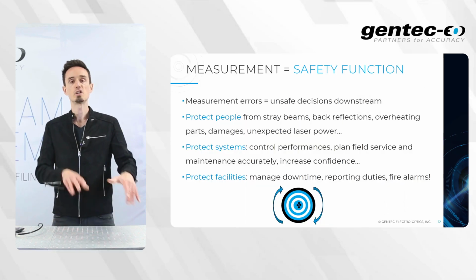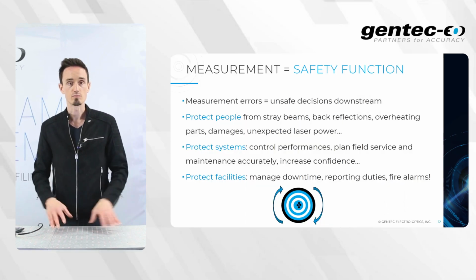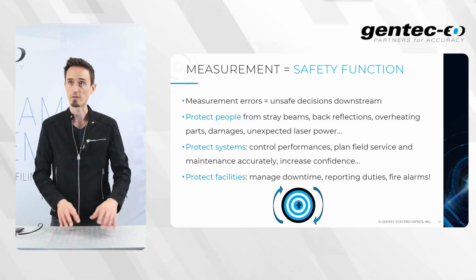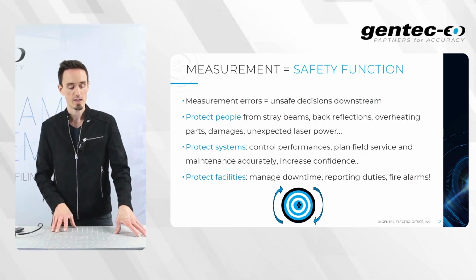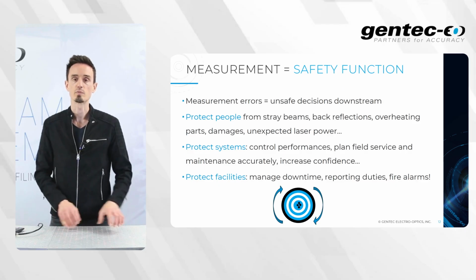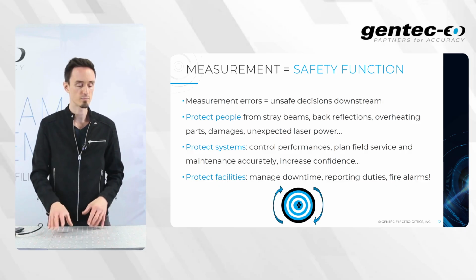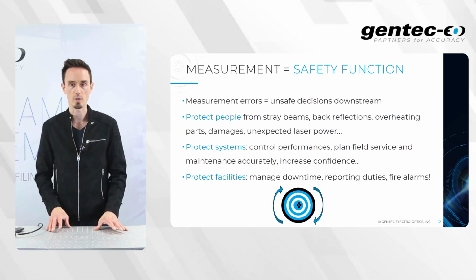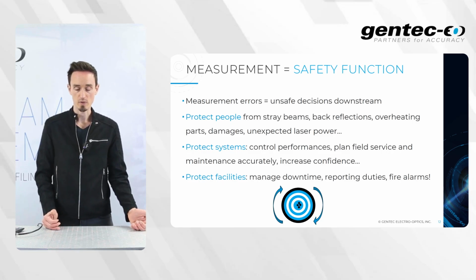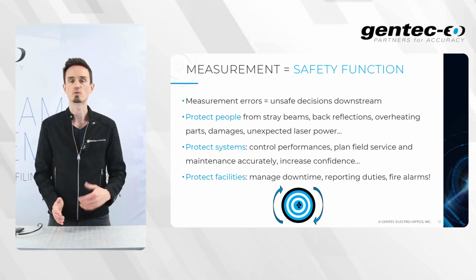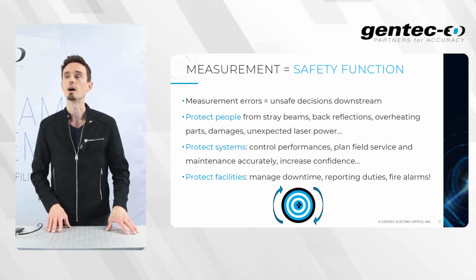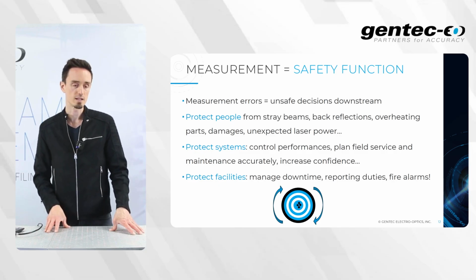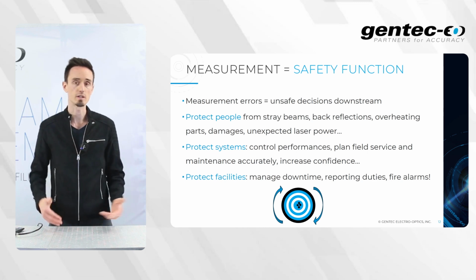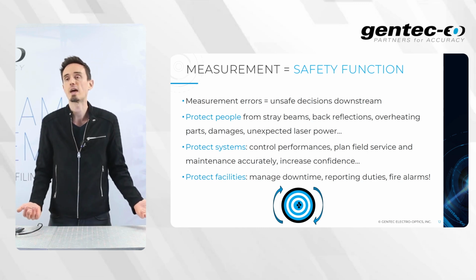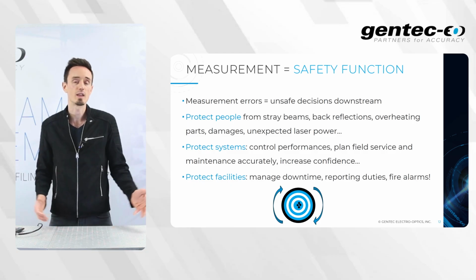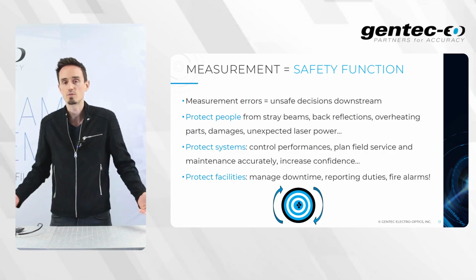Okay, so if we consider measurement as a safety function, then we acknowledge that measurement errors will drive unsafe decisions downstream, and then you will be able to protect people from stray beams, back reflections, overheating parts, damage, unexpected laser power, and so on. You will be able to protect the system if you integrate measurements this way, by controlling performance, planning field service regularly, or maintaining the system accurately, and increasing confidence. And then you protect the facility in the end, because you will be better at managing downtime, reporting duties, and managing those fire alarms. You don't want fire alarms.